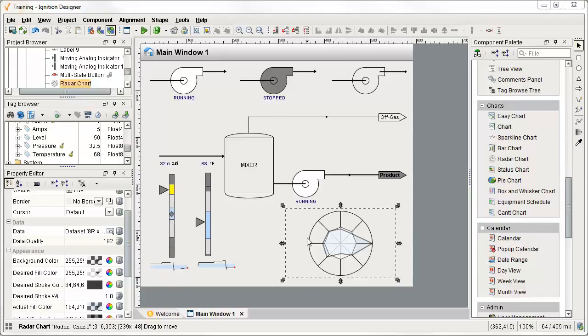The second polygon, the light blue semi-transparent one in the front, is showing us the current value of each of the process values. Since we want the process values to be as close to the set point as possible, the polygon should look like a circle. When the process value is outside of the set point, it is very easy for us to point out, like you see here, where the third one is clearly outside of the set point. The fifth one is inside of the set point. So essentially, it's easy for us to identify if multiple process values are within normal ranges or not.